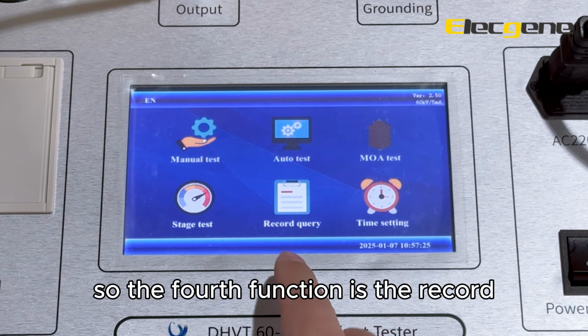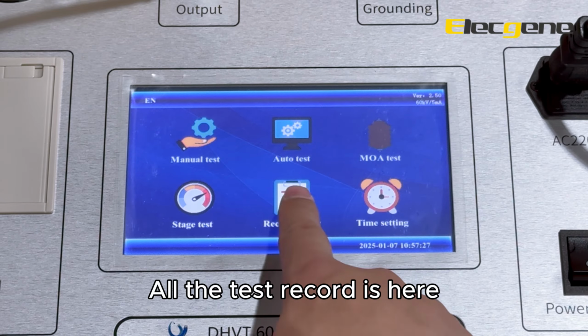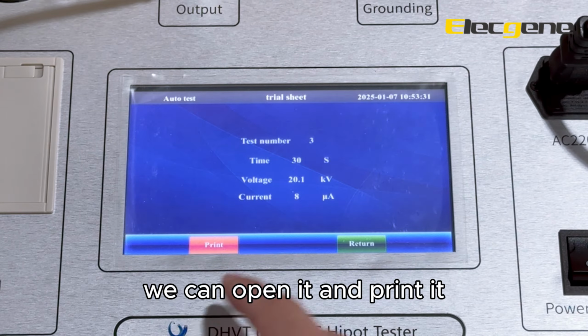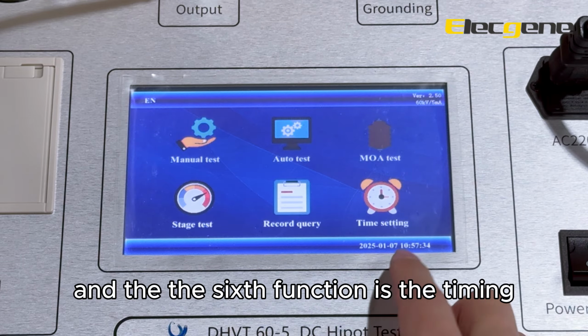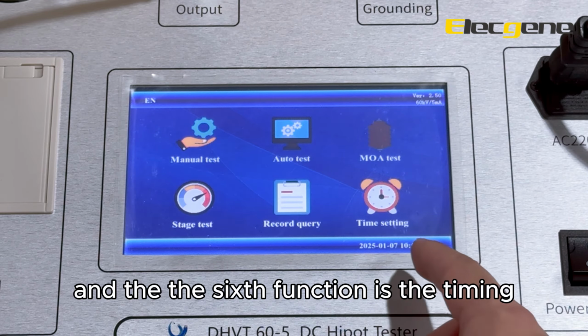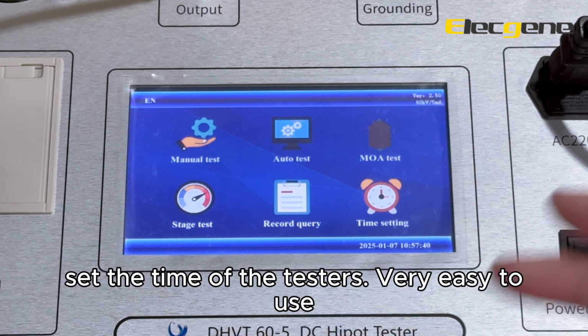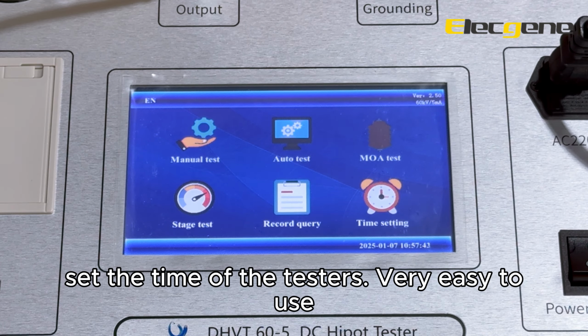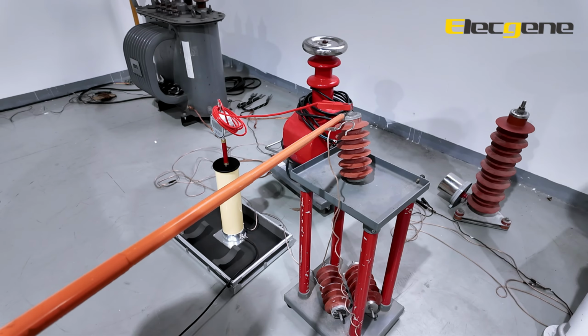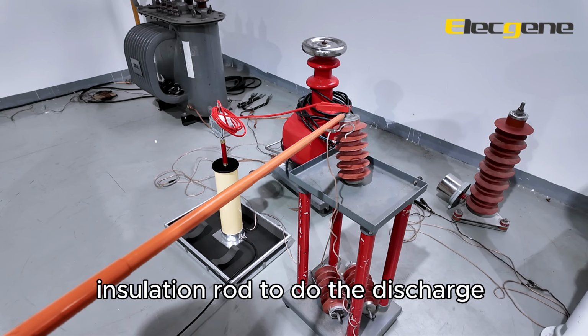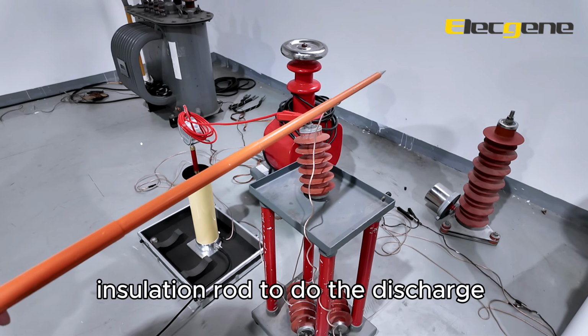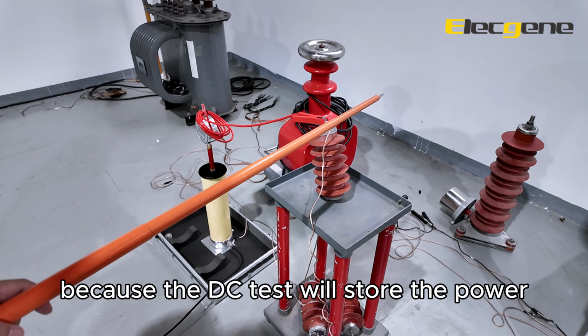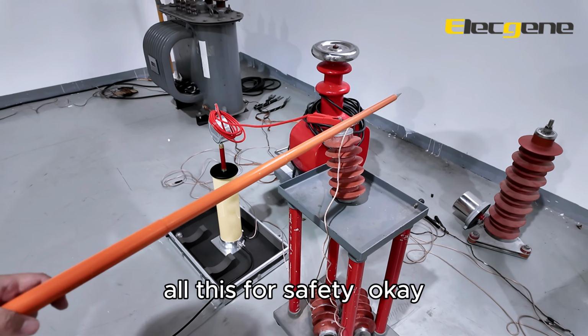So the fourth function is the record. All the test records are here. We can open it and print it. And the sixth function is the timing, the time of the testers. Very easy to use. After we finish the test, we should use the insulation rod to discharge because the DC test will store power. All this is for safety. Okay.